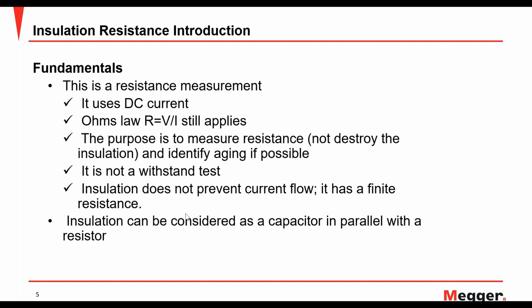Insulation does not prevent the current flow. It has a finite resistance, so always make sure that you are using a voltage that is appropriate for the type of equipment that you are doing it for. Let's say your motor or generator is only rated for 1000 volts. Don't do an insulation test of 2 kV or 2.5 kV.